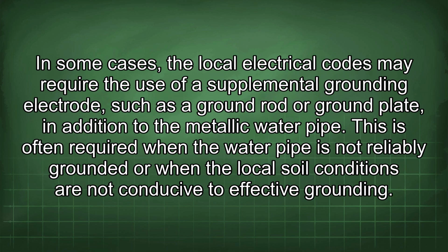In some cases, the local electrical codes may require the use of a supplemental grounding electrode, such as a ground rod or ground plate, in addition to the metallic water pipe. This is often required when the water pipe is not reliably grounded or when the local soil conditions are not conducive to effective grounding.